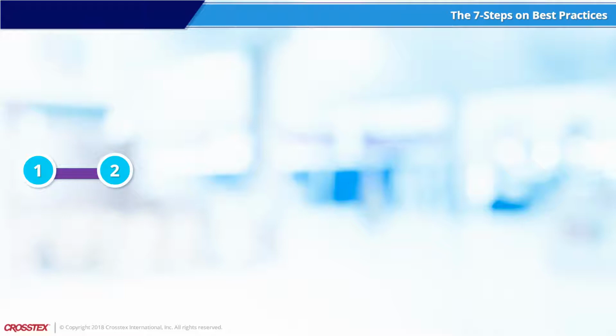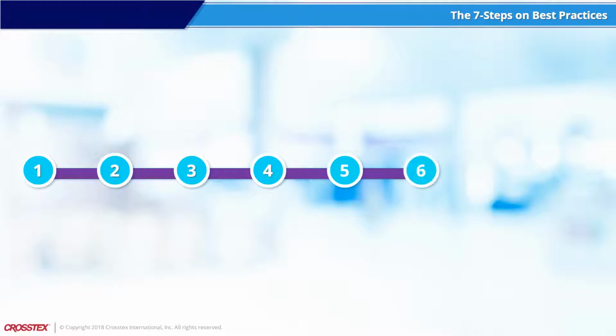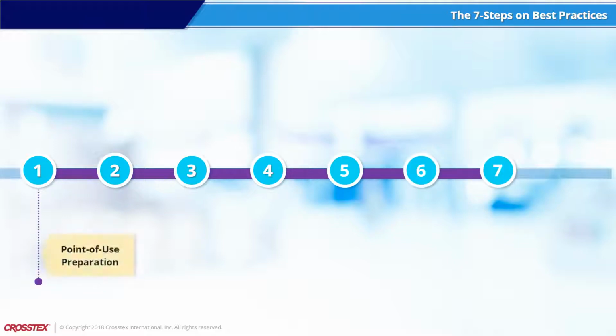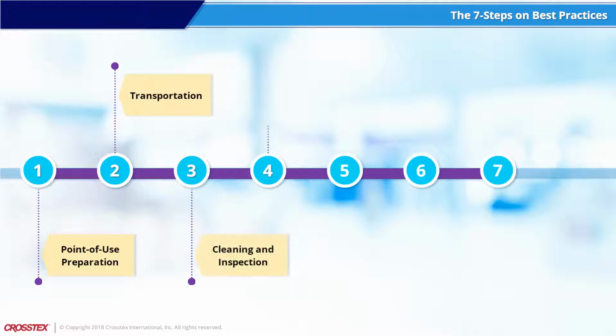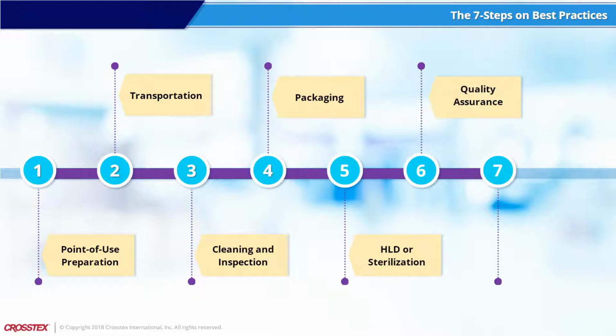The consensus includes 7 recommended steps based on best practice standards for medical devices and instrument processing. We begin with the point of use preparation, followed by transportation, cleaning and inspection, packaging, high-level disinfection or sterilization, quality assurance, and ultimately storage and delivery. Each step is based on specific procedures according to the guidelines, which can be implemented and managed at any type or size of medical facility.